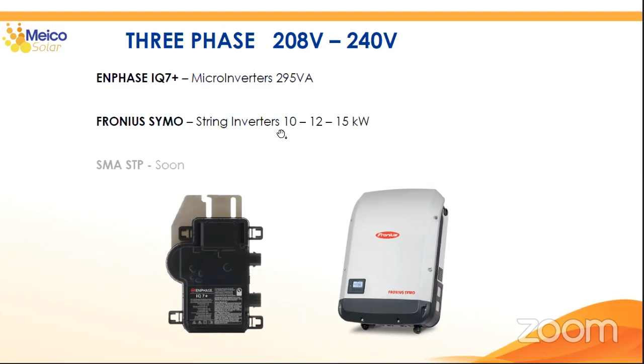Let's see how we can connect an ENPHASE IQ7 microinverter, which is a split phase inverter, in a three-phase connection. It's really easy. You have one microinverter per module, and you also have the possibility of doing grid zero even with three-phase. In this case, you have to build three circuits, three split phase circuits, as you can see here. The three-phase connection point has three lines and the neutral.